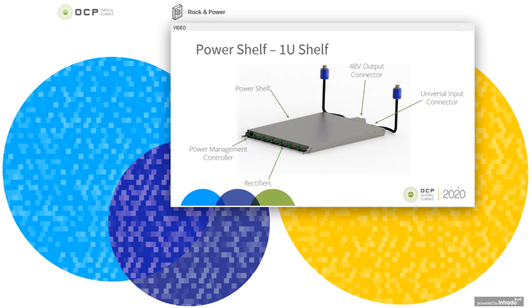The 2 1OU options have either 1 or 2 AC inputs bringing power into the shelf. This AC input connector is an OCP standard, the Universal Power Shelf Input Connector, which I will show in more detail in a later slide. The 48-volt DC output connector shown in the middle of the rear side of the power shelf interfaces toollessly with the bus bar in the rear of the rack and can power the entire rack of IT gear. This output connector is also an OCP standard, and we'll take a brief look at this as well.